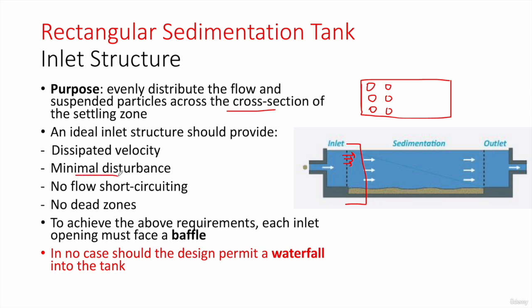We must limit any disturbance within the water so that particles can settle down; otherwise they will remain in the water stream and leave without meeting the sedimentation purpose. A well-designed inlet structure will also limit flow short-circuiting — when water leaves the tank without achieving the required retention time, either leaving quickly or taking a shortcut. This usually happens when the inlet is badly designed and the flow is not equally distributed.